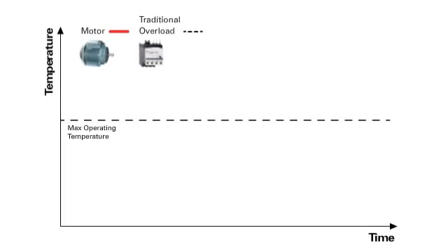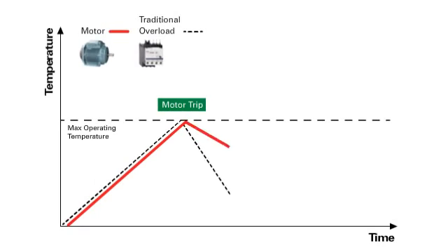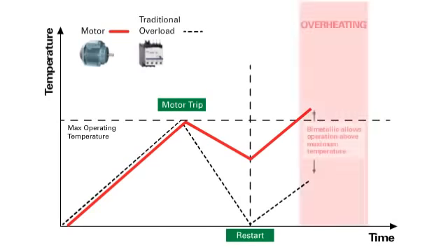Let's see how this happens. The motor, shown in red on this graph, runs until it reaches its maximum operating temperature. The bimetallic overload, shown in black, detects this and trips the motor. The problem is that the motor cools slower than the bimetallic and can be restarted sooner than it should. The bimetallic may allow the motor to run above its maximum operating temperature, which can cause damage.